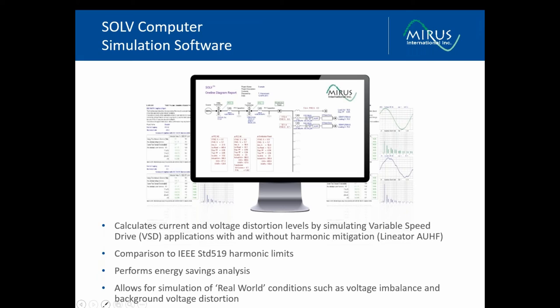And just to wrap up then, we've developed a proprietary computer simulation software called SOLV, but it is free and available for any engineer, consultant, or OEM to download to run their particular applications to determine the current and voltage distortion levels. It will compare these to IEEE 519 harmonic limits, which then can be related to the marine standards, depending on which certifying body you need to meet. Software is available, as I said, at no charge.